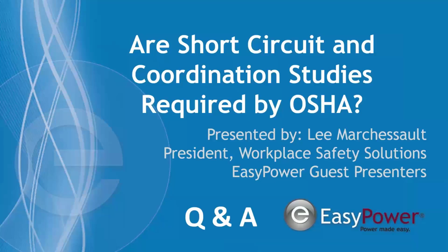Right. And then the last question, another one that comes up frequently: are arc flash labels for equipment controllers required for VFDs? That's a really good question, and a tough one too, because you could have various results at various parts of the operation, so you end up labeling for the worst case scenario, and sometimes it ends up being at high levels because of the clearing time issue with the VFDs. It gets a little more complex, and so that's something that's case by case.